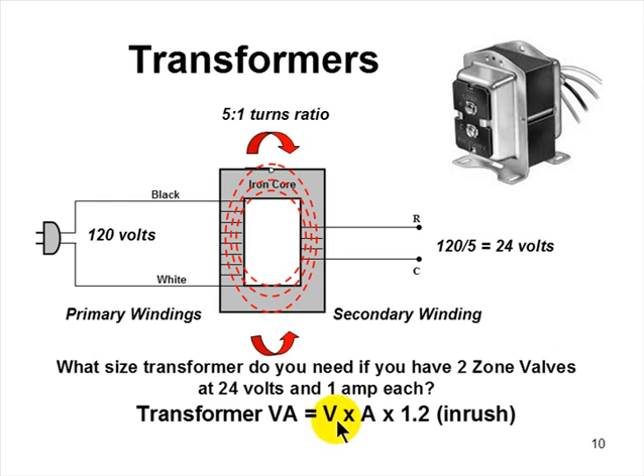In the case of a 24 volt circuit, it's not 4 to 5 times, it's only about 20%. So inrush current is always greater than running current, and in this case by 20%. So what's the formula? Volts times amps times 1.2. Well, they're 24 volt motors, there are 2 of them at 1 amp each, times 1.2, 57.6 VA.